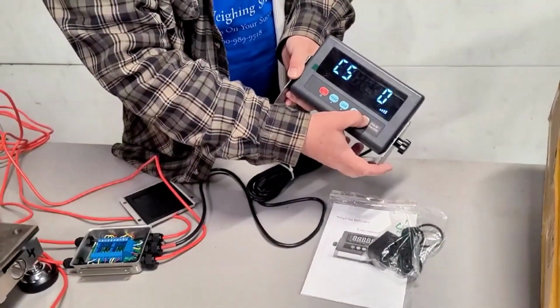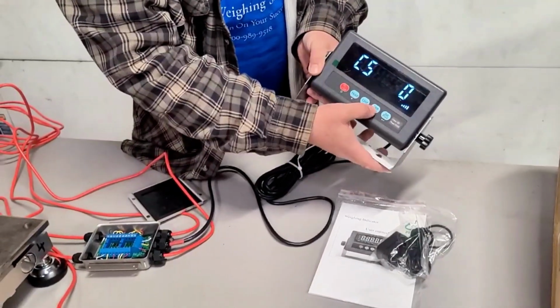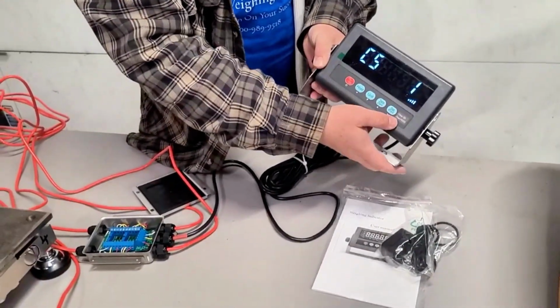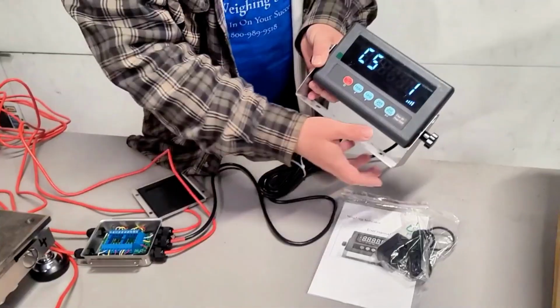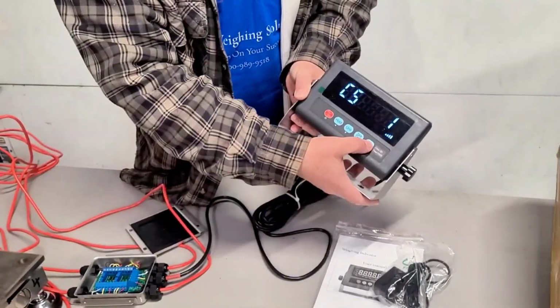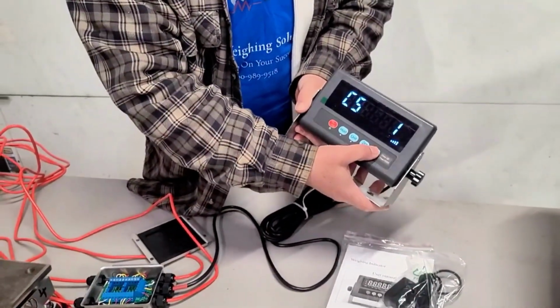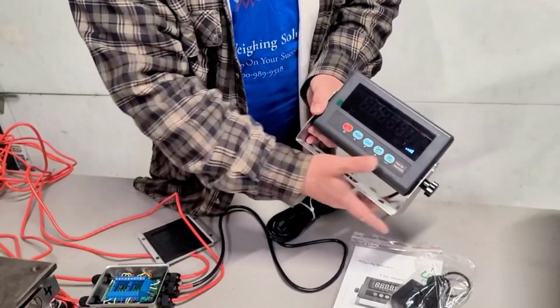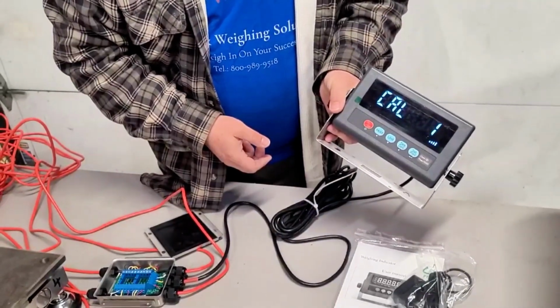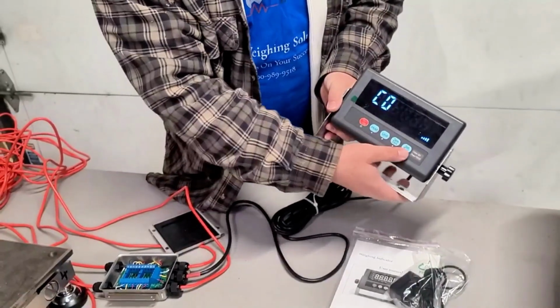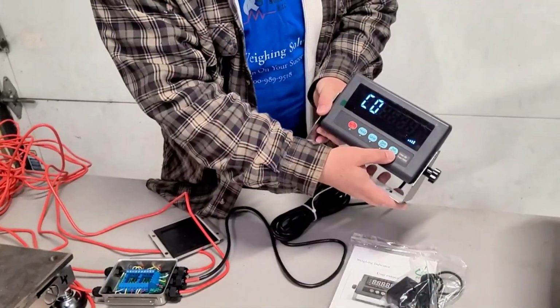C5 is your 0 calibration. It comes up with 0. We change that to 1 in order to actually give a new 0 calibration to our new frame, because at this point the indicator doesn't know what it sits on, a load cell. It'll count down. As soon as that happens, it goes to 0. You press set. It goes to the next parameter, which is span calibration.